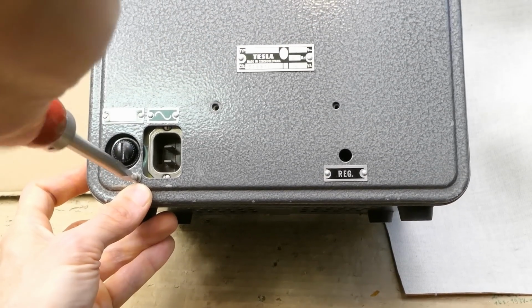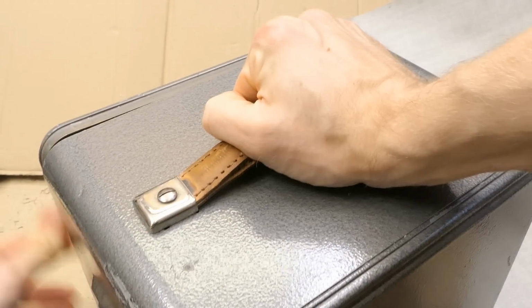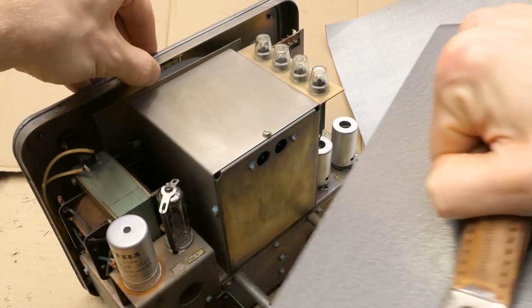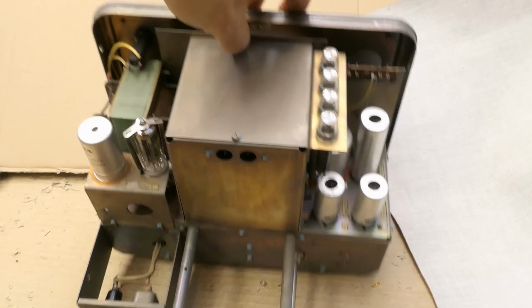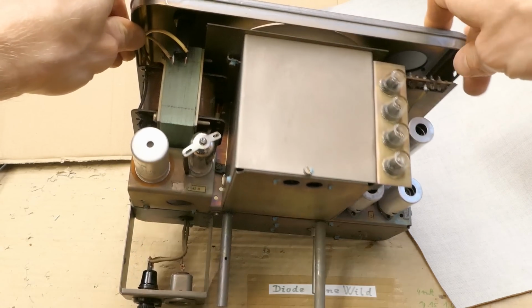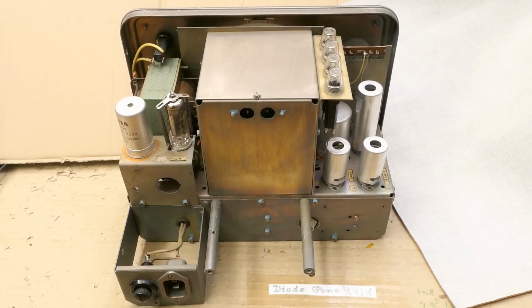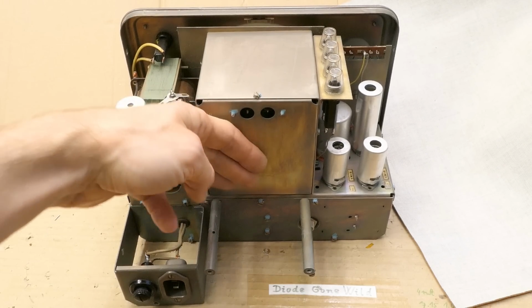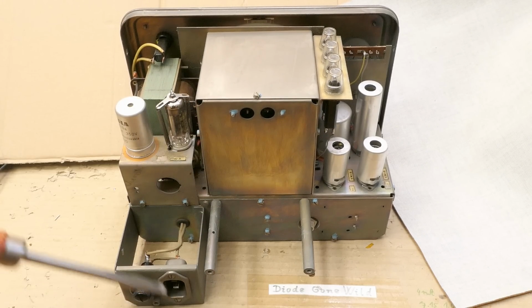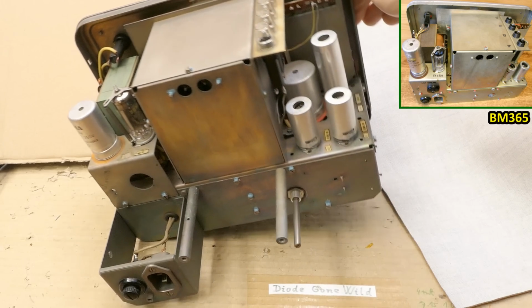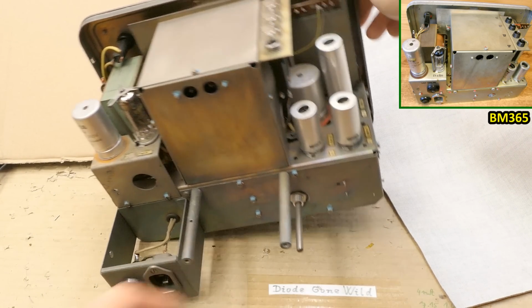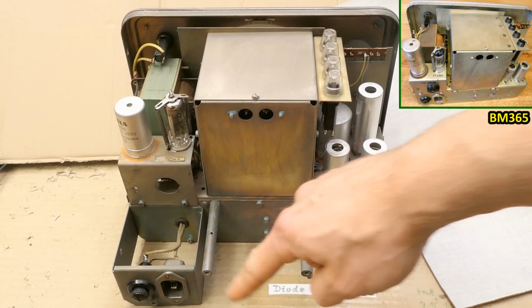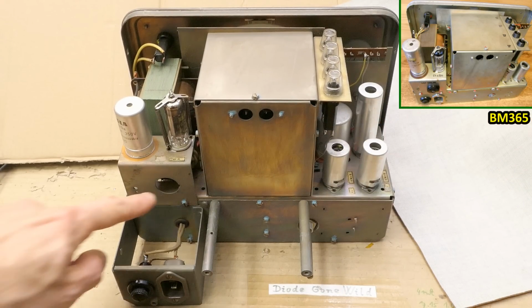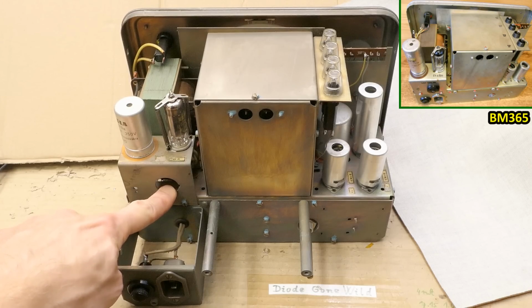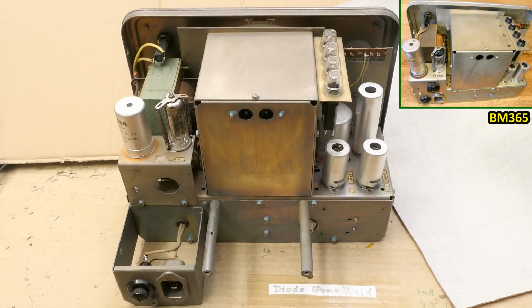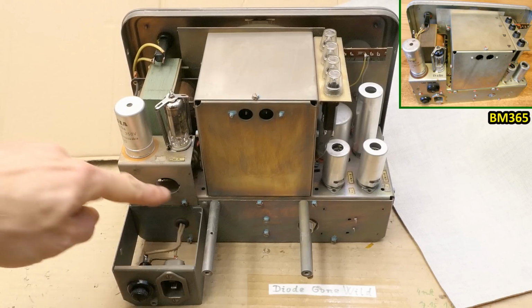One extra screw here in this one. And the back comes off, or at least it should. And that's it, the internals. Here you can see how almost half of the box is actually empty. In the previous version, the back of the box would be right against this chassis. The fuse holder and mains in connector would be sunken in this. This potentiometer here would have just a slot, no shaft. These would be just holes in the chassis for screws, not these pillars. And the mains voltage selector, 120 or 220 volts, would be here. And the back of the box was originally right against this, but now the hole for the selector is sunken deep inside of it.